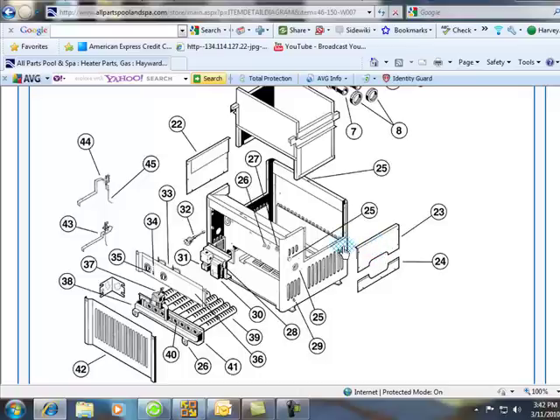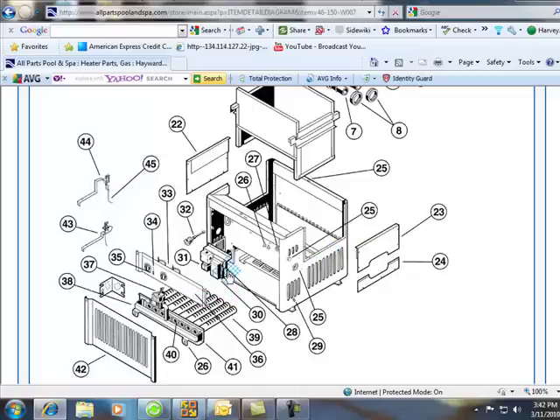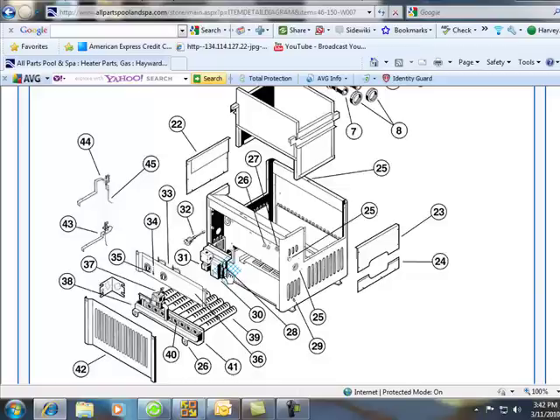So we need to pull out our meter and check for continuity. Now, a millivolt heater doesn't push voltage, so everything on your meter has to either beep or show zero. So it has to show a dead short to it.